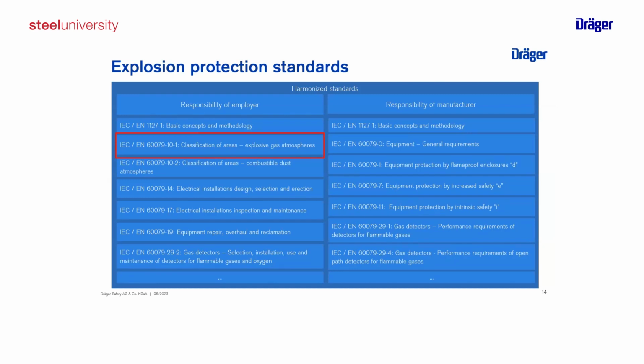And there is the IEC EN 60079-10-1 for gases. Another one which we will also cover in this presentation is the IEC EN 60079-29-2. This is about gas detectors, meaning selection, installation, use, and maintenance of detectors for flammable gases and oxygen. If you have guidance on how to select, I think we also need a standard which defines the performance, to define criteria for detectors which can be used and should be linked to the selection process. So these are, I would say, 3 relevant standards, and in my presentation we will later hear what the content and meaning of these are.